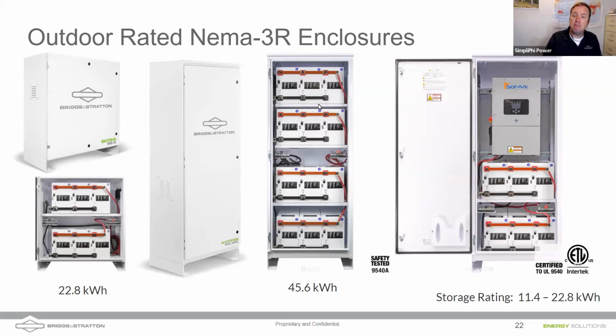Boss 6 cabinet on the left-hand side, we'll show you here in a second, you can put heating pads underneath these batteries so they're thermostatically controlled. They use about 45 watts, and they're not going to run continuously. They'll cycle on and off to keep the batteries warm, allowing you to run them in cold weather applications. Further, we can take our access cabinet and put either a Sol-Ark or our inverter, our 6K inverter, on the top half of the cabinet, and on the bottom we have the 6 batteries as well.